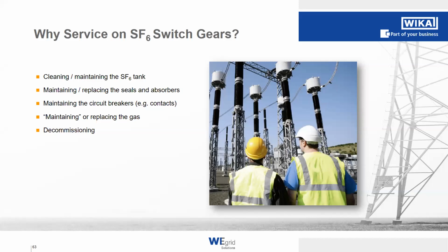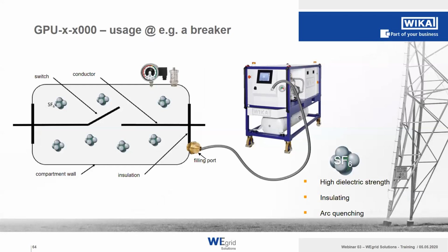So also when you are maintaining the circuit breakers, for example, the contacts, which could corrode over time, depending on the humidity level in your gas, and you also need to just maintain or replace the SF6 gas. And within the 4 stages is also the decommissioning stage, when you're disassembling your unit or the gas insulated switchgear, for example, then you have to decommission it at the end and pull out all the SF6 gas. So these are the areas where the GPU-X is operating.